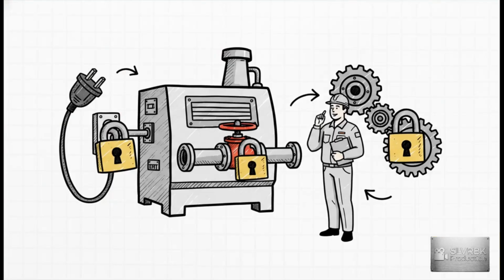It all starts at the top with the employer's fundamental mandate. OSHA is crystal clear here. Employers absolutely must establish a formal, documented energy control program. The whole goal is to guarantee that employees isolate machines from their energy sources, whether that's electrical, mechanical, hydraulic, pneumatic, chemical, you name it, and render those machines fully inoperative before any servicing even begins. Look, if there is even a slight potential for unexpected startup or a release of stored energy, this program has to be firmly in place to protect your team.